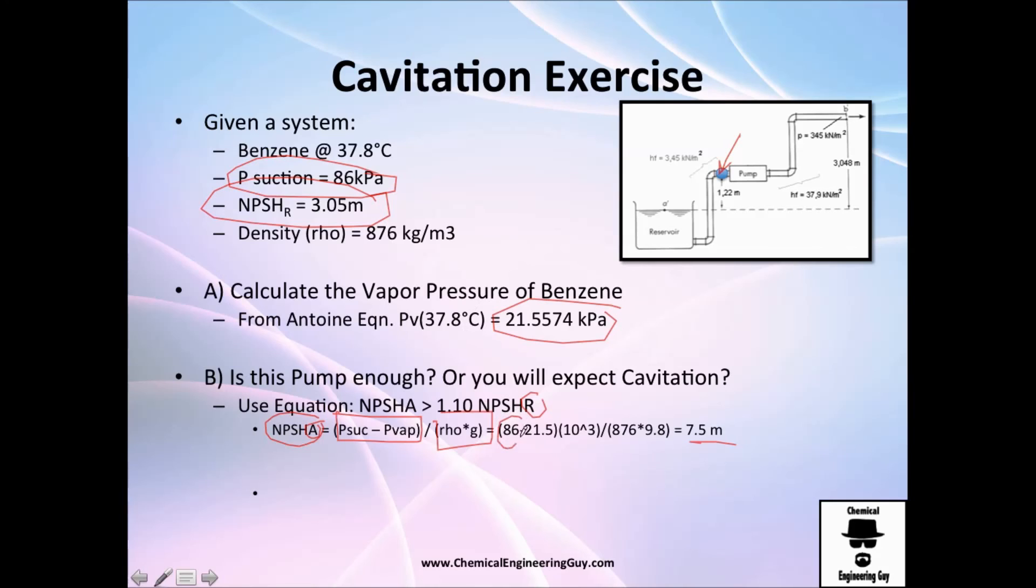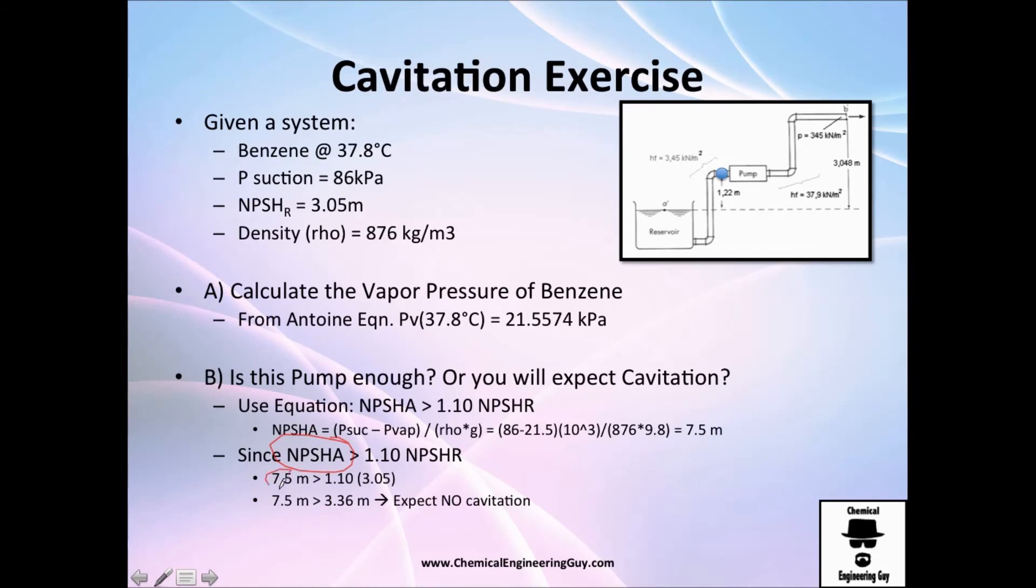Doing this, I got pressure of suction minus vapor pressure. Be sure to change everything to Pascals. We are working right now with kilopascals, so we need to multiply this by 1000, divided by the density and gravity, and I got this value of 7.5 meters NPSH available. The criteria for cavitation is the rule: I got 7.5, is it bigger than 1.10 times the NPSH requirements? Yes, I think it is. I have 7.5, is it greater than 3.36? Yes, it's great, so we will not have cavitation. That's awesome.